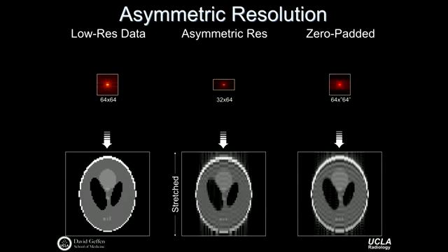So I sort of mixed up the examples here. Here I was saying if I just actually stretched it, I would recover this image. The other option is to actually zero pad it. And if I zero pad it, you can see that those same pixels now are individually square. So just by stretching, I have rectangular pixels, and that might not be preferred. By zero padding, I haven't added any information, but they'll show up as coefficients in that Fourier sum, such that my pixels themselves will now be square again. And that might be a more useful thing. We'll talk about some of these other artifacts and problems that you're seeing in this reconstructed image in just a second. So bottom line, zero padding is useful for reconstructing pixels as square.